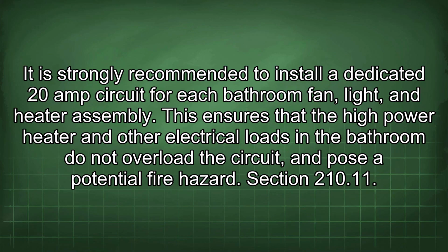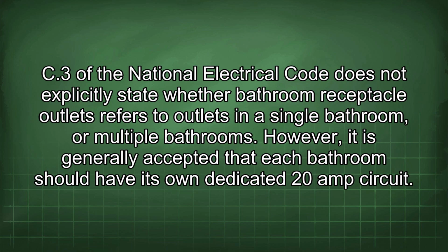It is strongly recommended to install a dedicated 20-amp circuit for each bathroom fan, light, and heater assembly. This ensures that the high-power heater and other electrical loads in the bathroom do not overload the circuit and pose a potential fire hazard. Section 210.11 C3 of the National Electrical Code does not explicitly state whether bathroom receptacle outlets refers to outlets in a single bathroom or multiple bathrooms.